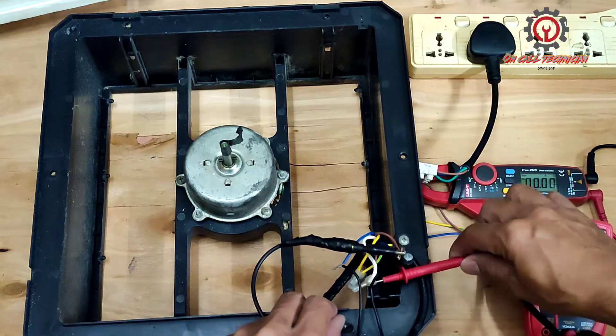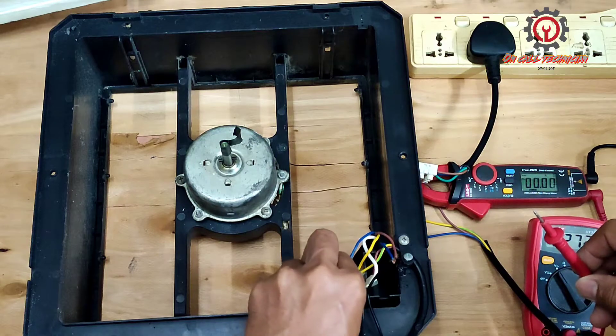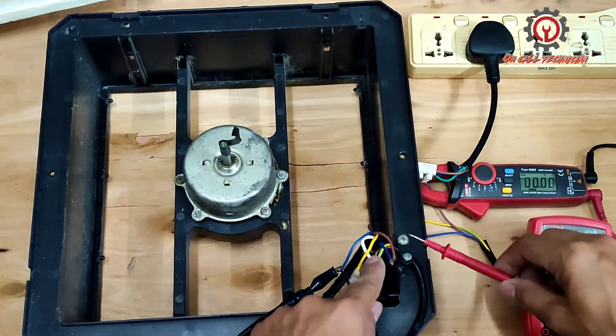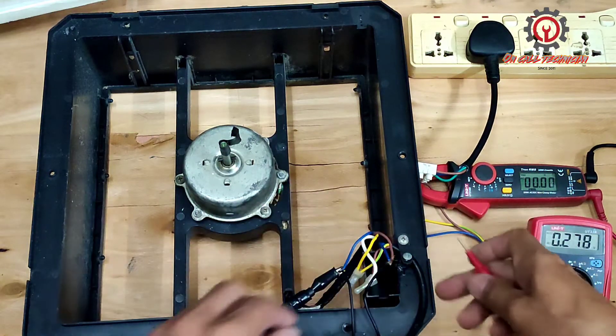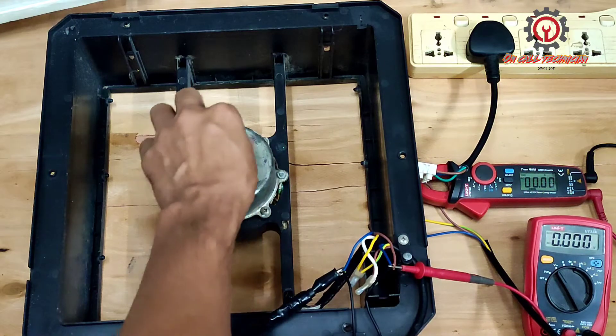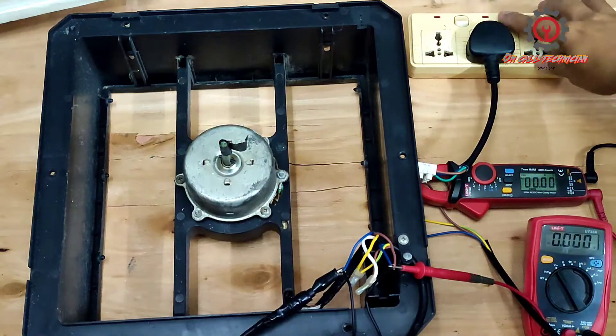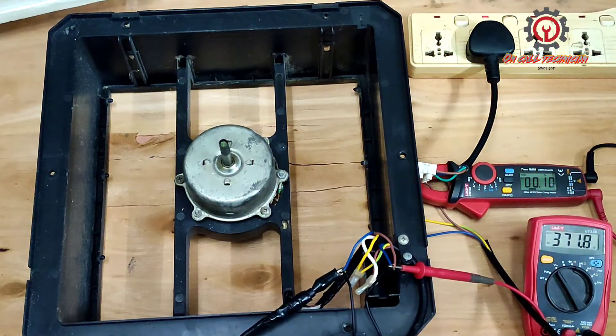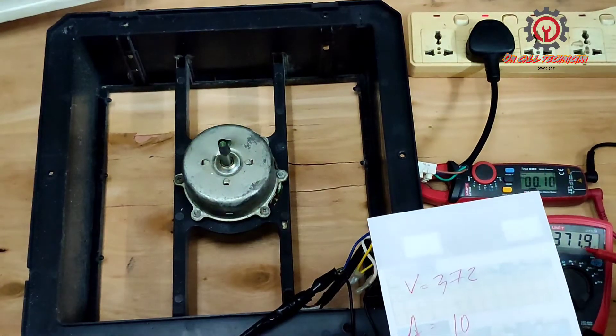But now I'm going to plug in this one here so we can take a measurement from the starting terminal and from the common terminal. We're going to measure the voltage — just set it to auto. I'm going to show you that this one is spinning because this is the air connection. Take a look — we got 371 volts here and 10 ampere for this capacitor.